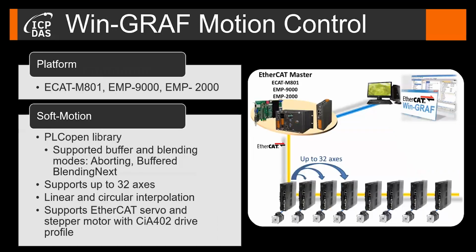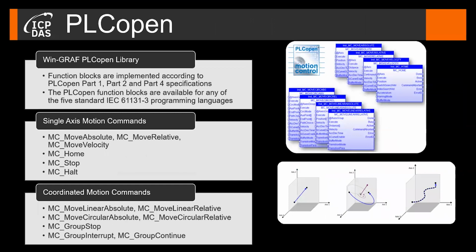All three EtherCAT-based soft PLC types have an integrated motion controller. The motion control function blocks are implemented according to PLCopen specifications. Most PLCopen defined single-axis and multi-axis function blocks are available. Up to 32 servo or stepper axes can be controlled synchronously. All drives with CiA 402 profiles are supported.